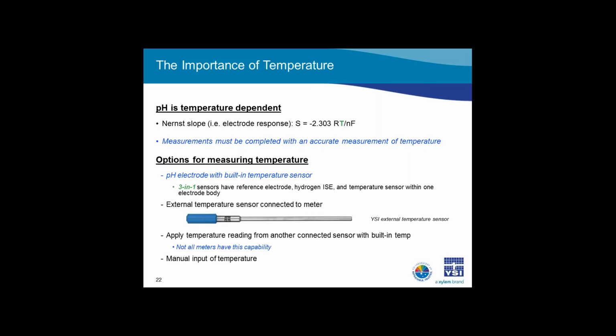With today's pH systems, you have some options for measuring temperature. The best option is to select a pH electrode with a built-in temperature sensor. When pH electrodes have a built-in reference electrode and temperature sensor, they are commonly referred to as a 3-in-1 sensor. The next best option is to supply a temperature reading directly to the instrument via a standalone temperature sensor. Most meters allow you to directly connect a temperature sensor. You just have to make sure that this temperature sensor is in your buffers during calibration and in your sample during measurement.